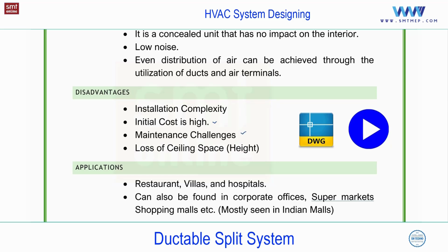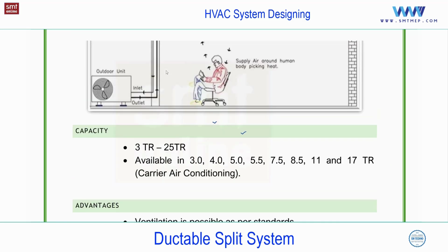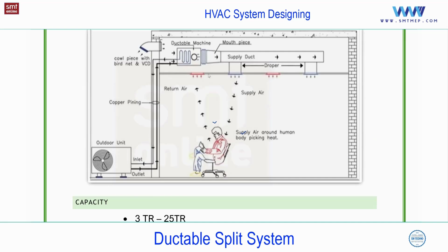Maintenance, because you see this unit is concealed. Anyhow, in actual practice, below the unit in the false ceiling, you'll find the trap door. The trap door is for maintenance. In case of grid false ceiling, I believe everyone knows what a grid false ceiling is. Grid false ceiling means you'll find the tile, or tile false ceiling, pieces of tiles. So in case of tile false ceiling, one can easily remove the tile and maintenance can be achieved. Or in case of gypsum false ceiling, you need a trap door. You'll find a separate trap door in case of any maintenance or changing of filter, etc. So maintenance requires proper access, compared with the split system.